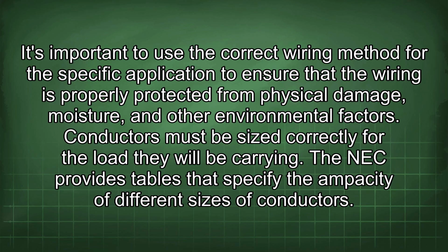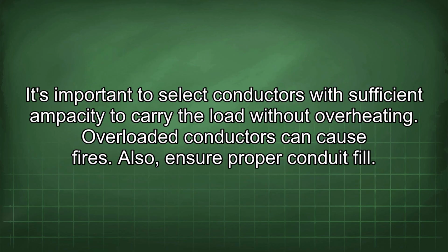Conductors must be sized correctly for the load they will be carrying. The NEC provides tables that specify the ampacity of different sizes of conductors. It's important to select conductors with sufficient ampacity to carry the load without overheating. Overloaded conductors can cause fires.